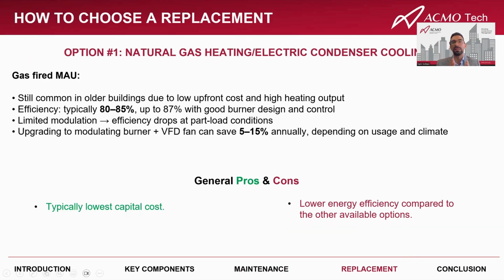When we go down the path of replacement of a makeup air unit, there are various options that you should know about before deciding if a re-and-re is the best option or if some sort of an upgrade makes more sense. The most common option, of course, is the natural gas heating, where you have a gas line directly going to the makeup air unit, and the cooling is provided by an electric condenser that could be attached to the unit or it could be remote. These are the most common type of units inside the condominiums and typically have the lowest capital costs, but also have the lowest energy efficiency. They could be upgraded to increase the efficiency by having a modulating burner and VFD added to some of these existing units if they're not up for replacement.